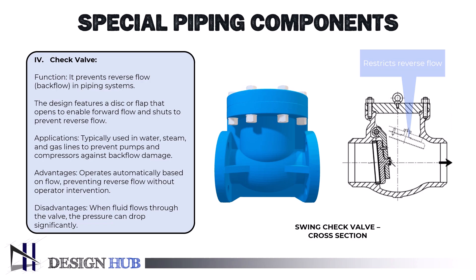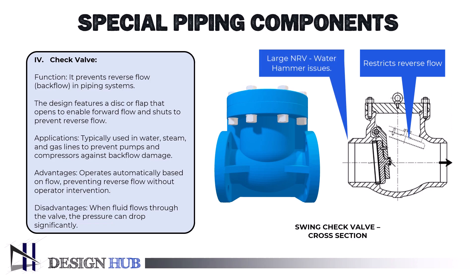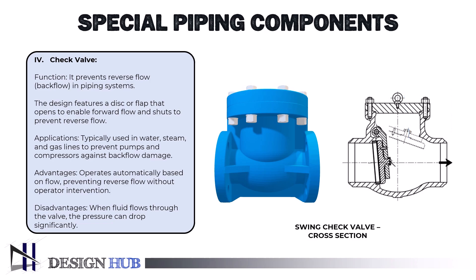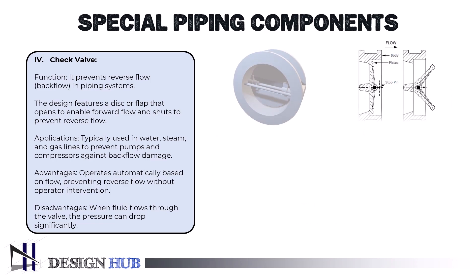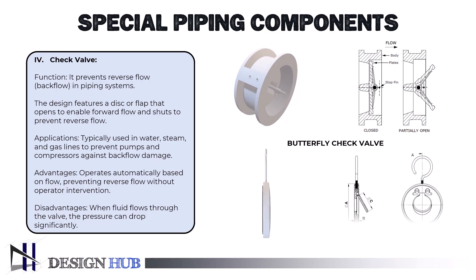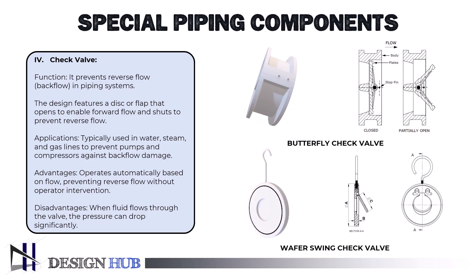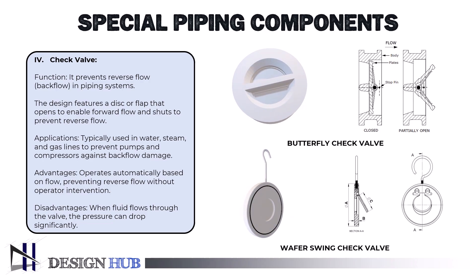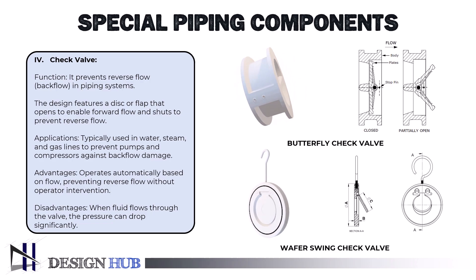Here we have a swing check valve. A swing check valve has a disc that swings on a hinge to block reverse flow or allow forward flow. The seat opening can be perpendicular or angled. Large check valves are often swing check valves and may cause water hammer issues. A butterfly check valve is not the same as a butterfly valve; instead, it functions as a check valve to halt backward flow, while a butterfly valve regulates flow in both directions.